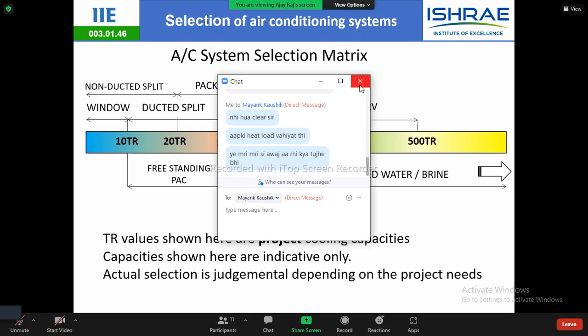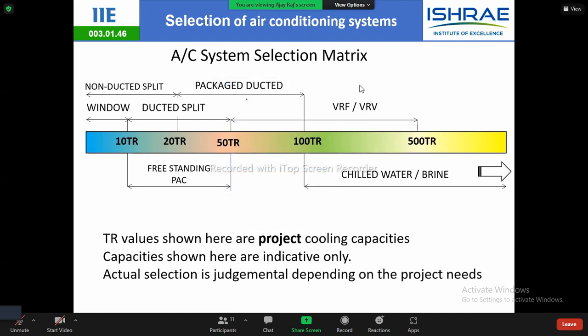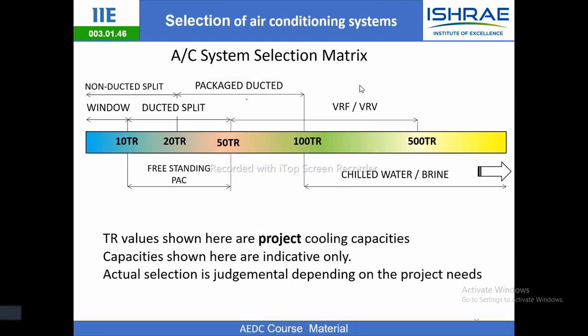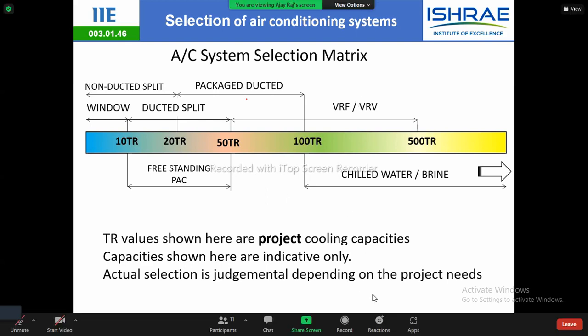For example, let's say you have a mall, and in the beginning only the ground floor is going to get occupied. So if you go with VRF system, for the number of shops you sell, only those VRF systems you have to put. Whereas if you go for a chilled water system, you have to go for a total one system. So in the initial phase itself, you have to go for a bigger initial capital cost.